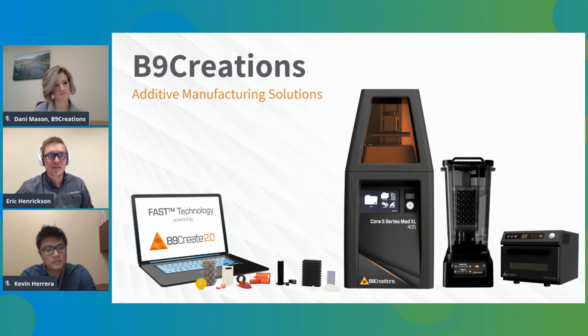The main features of the materials are the durability. It's actually a polishable material, which is pretty cool. We have a couple customers that are actually dyeing the white material, so you can use it more in an end product sense, even if it's just to show, hey, this is what it's going to look like in the real color later. We've found value in that for a lot of teams. It's also sterilizable. Regulatory wise, it's ISO 10993 compliant. That means it's okay for continuous skin contact of unbroken skin for up to 30 days.